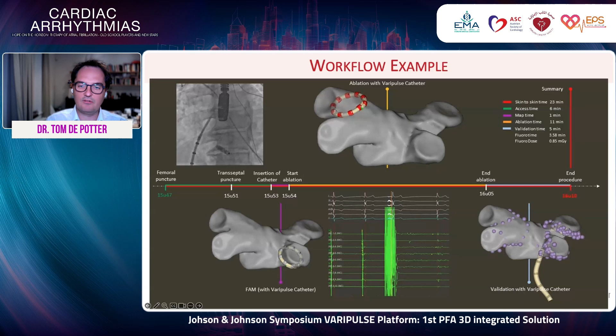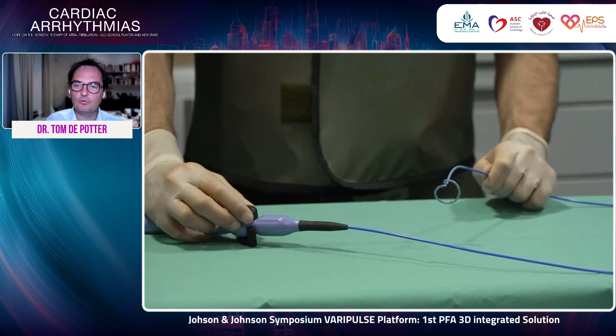So this is a video we recorded for a live case of the technology. You can see here the catheter itself. You can see that the loop is variable, as discussed already, 25 to 35 millimeters. It has a handle to steer. It is bidirectional.